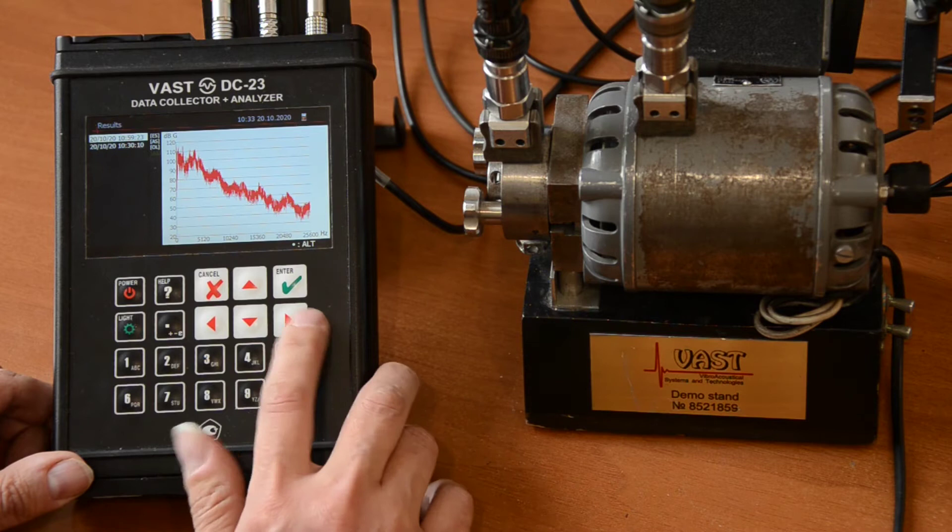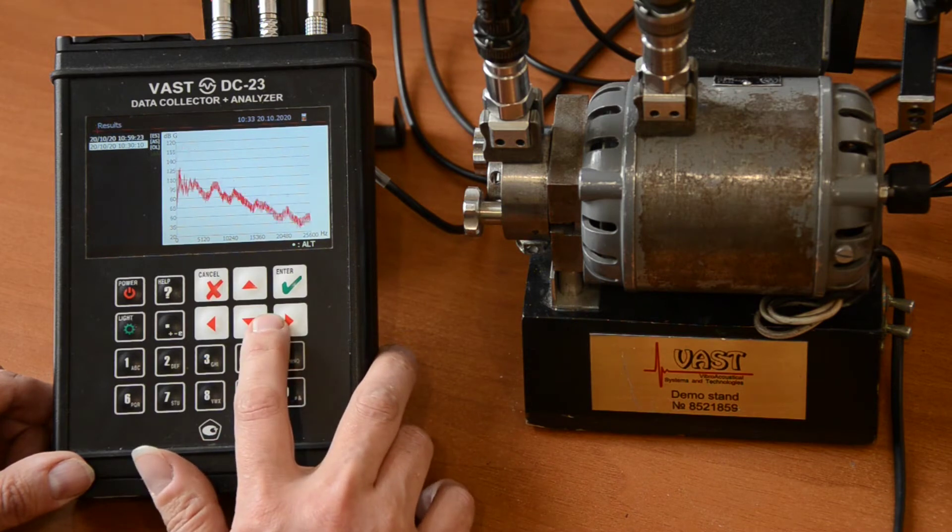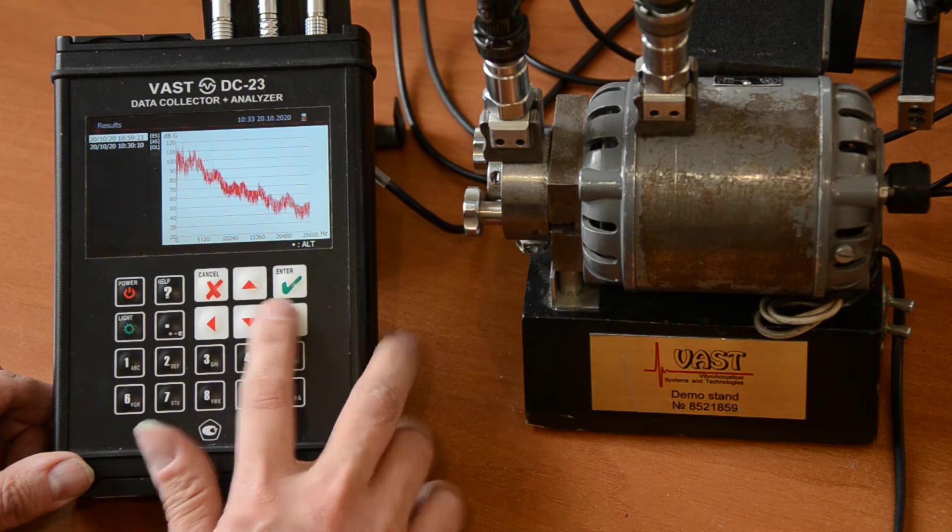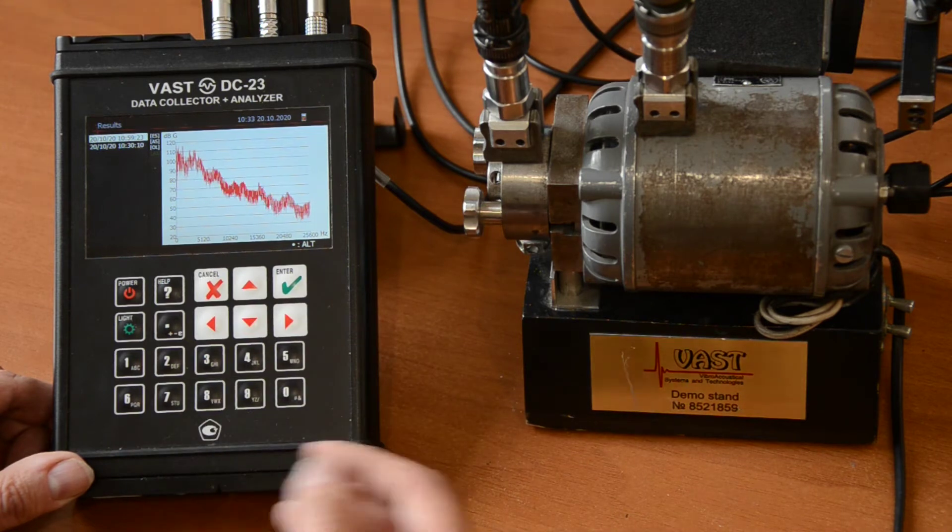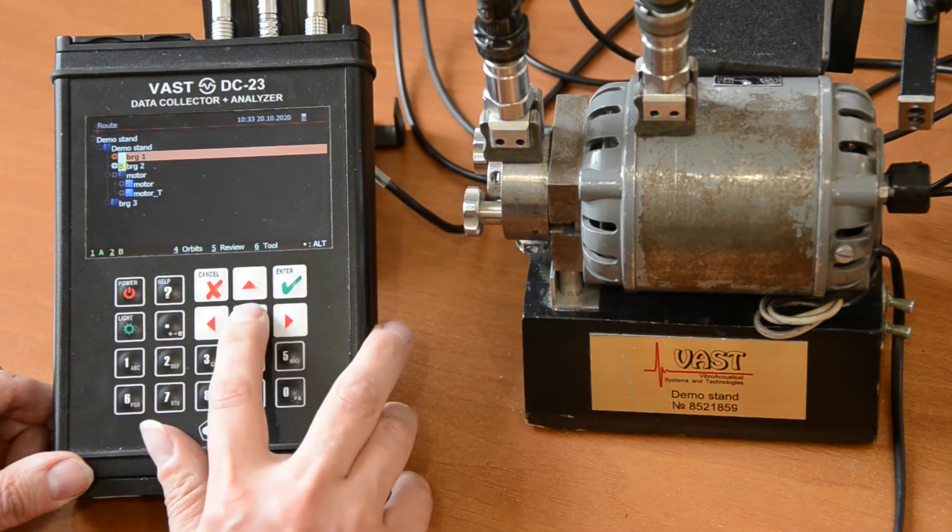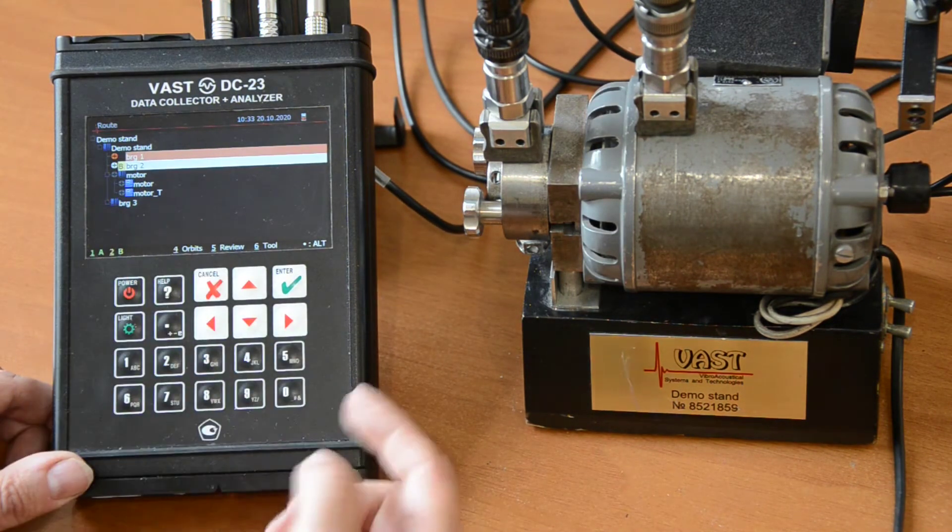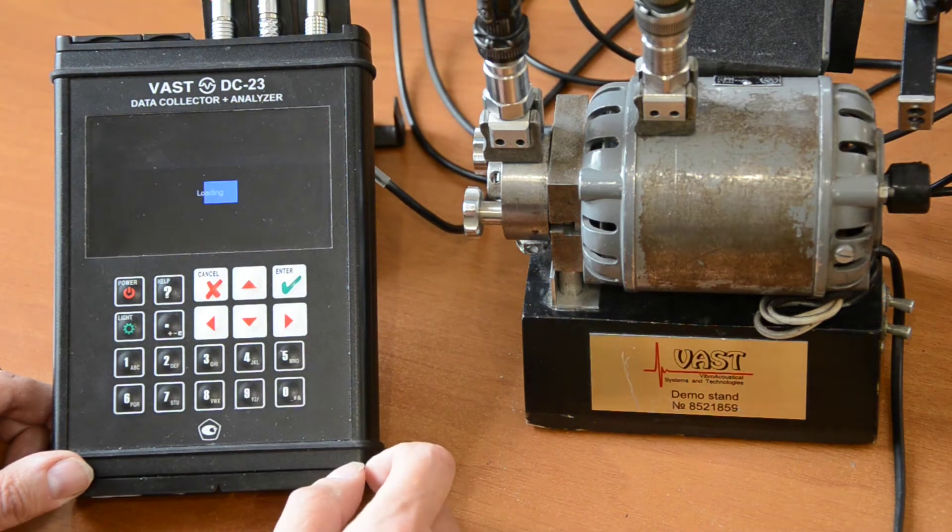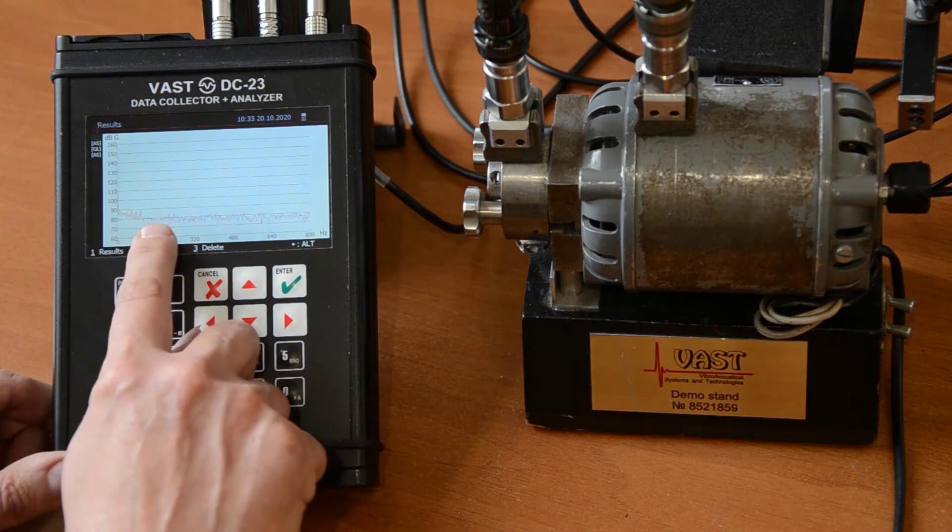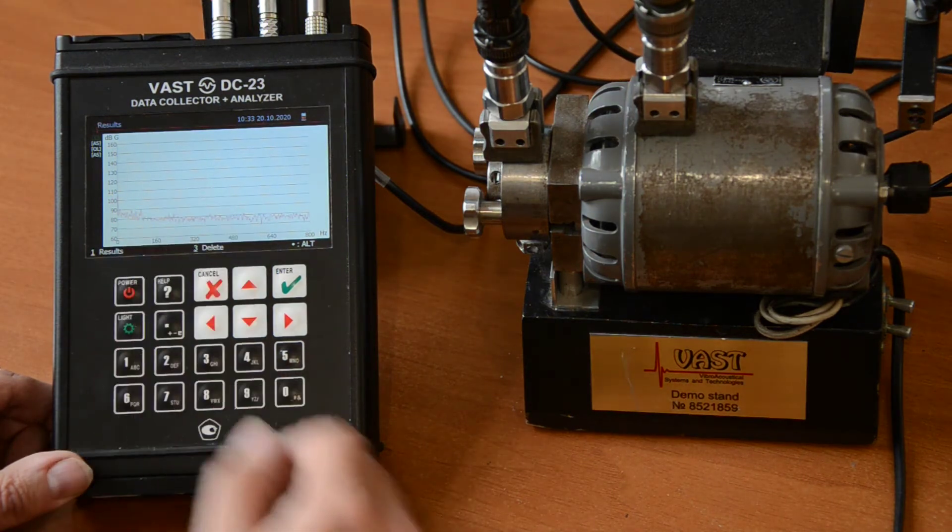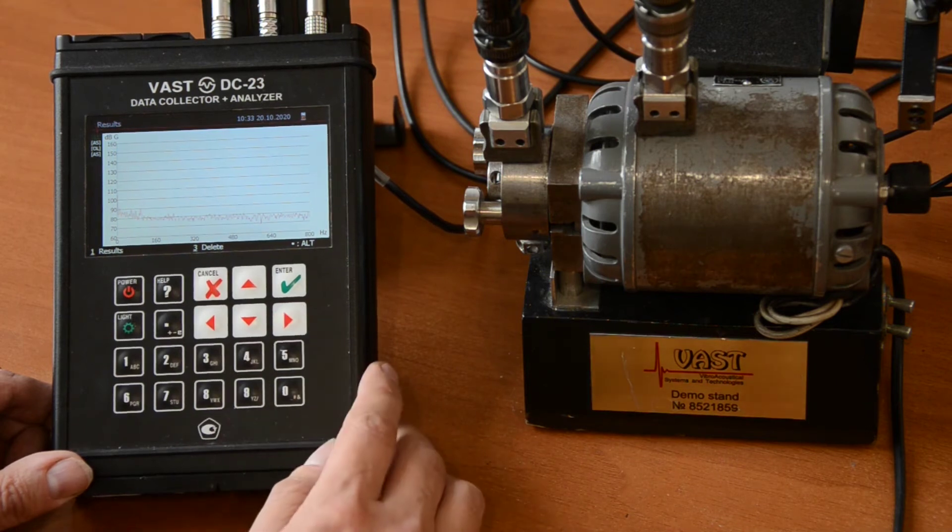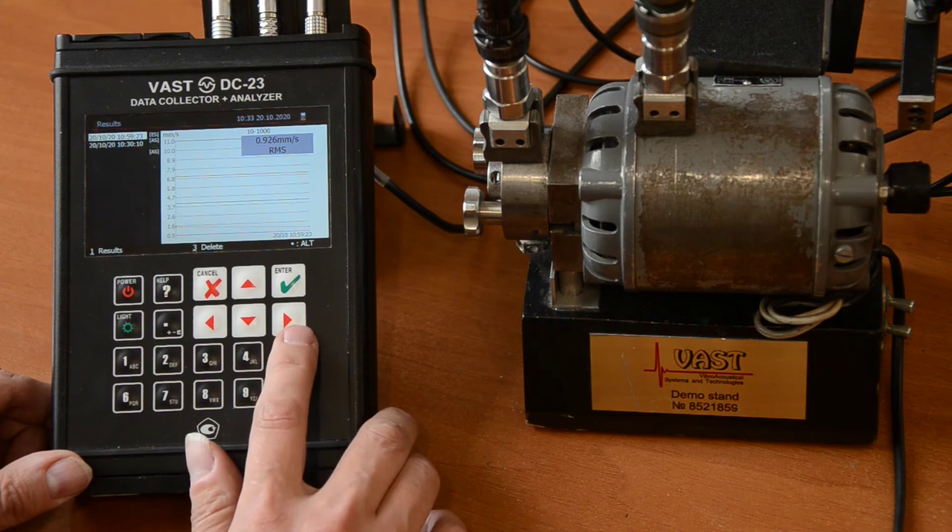So, also we have the two different spectra from the previous measurement and from the current measurement. We can just compare it. Actually, the same with all the measurements. If we go to the bearing number 2, we can also review the data and see that the spectrum here, this is the envelope spectrum, is very different from the previous one. And we can go to another measurements as well. This is auto spectrum. This is overall level.